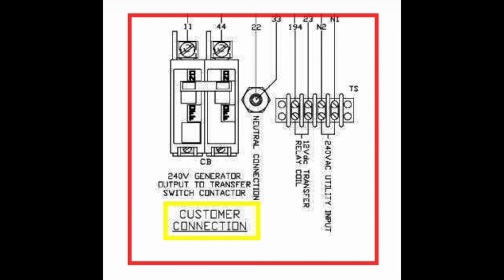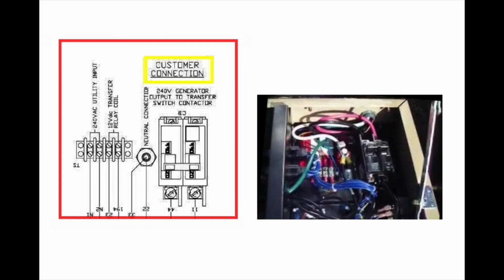And then your control circuits, which will be a block of connectors where the wiring will be attached for the controls. These controls will activate sensing relays that sense the power loss from the utility, have the generator start up, and once it's up to speed and you've got full voltage, then of course the generator transfer switch transfers over. So we make those connections at the generator. It's pretty basic and straightforward.